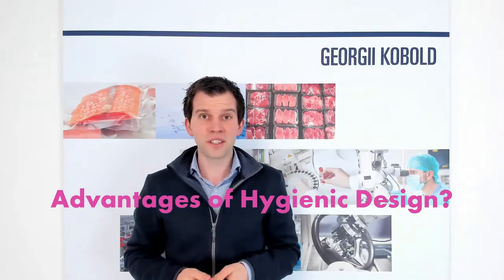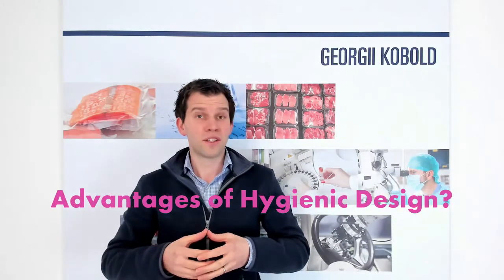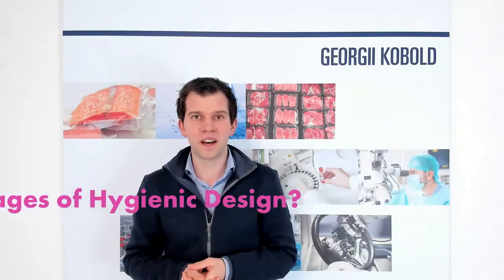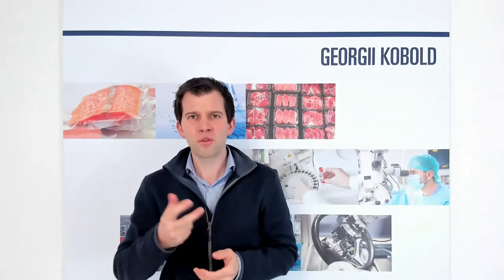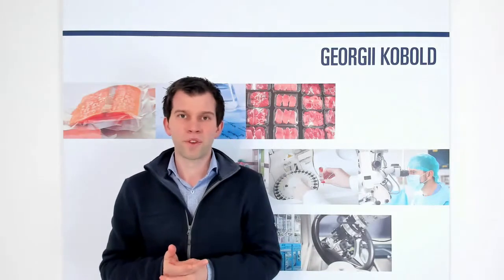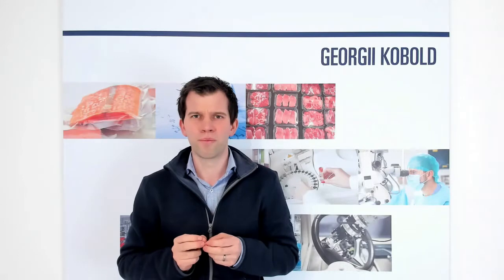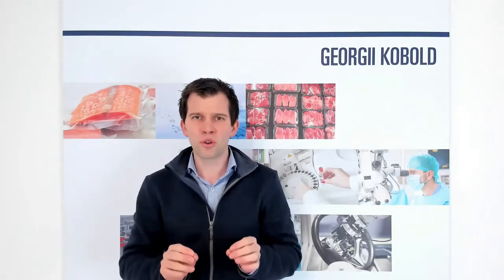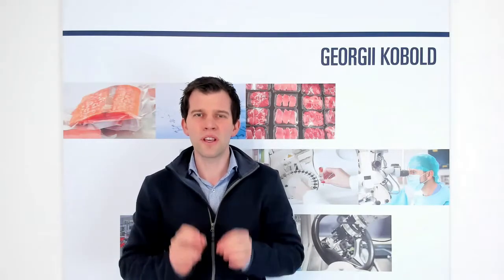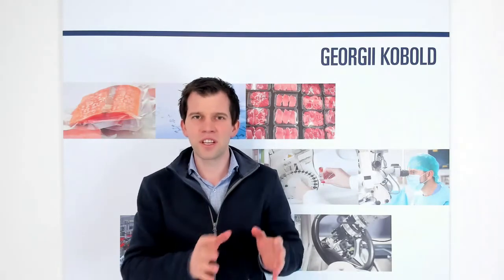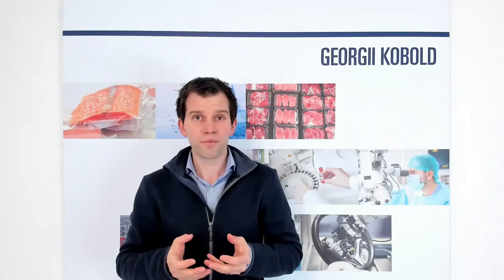The second question is, what are the advantages of hygienic design? And we can mention three very important benefits. First, you reduce the risk of contamination of food. And therefore you can save a lot of money because these motors can be cleaned very easily. You can use aggressive cleaning agents. You can clean them with a high pressure cleaner. They have a sealing with IP69K which fulfills these demands.